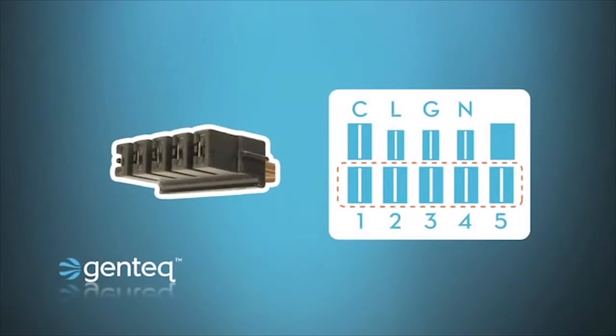Now we see a picture of the low voltage connector, and it also has been designed so that it can only go in one way. On the lower portion of the connector, there's a large lip on the connector so that if you turned it around, it would run into the wires that are connected into C, L, G, and N. Therefore, this can only be plugged in where the terminal 1 wire goes into terminal 1, and so on and so forth. Now, with all that said, the manufacturer does not have to use these plugs, and some may not.